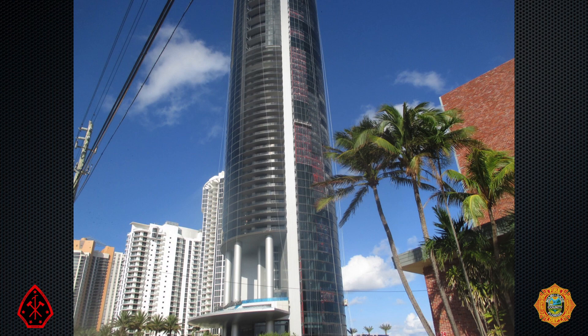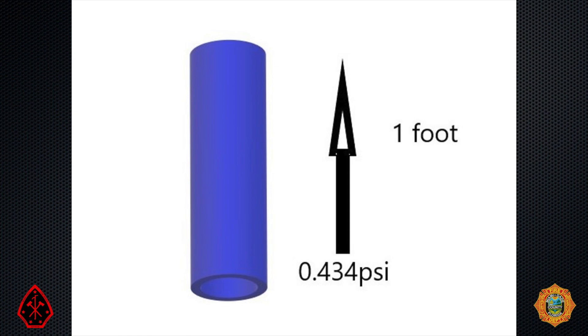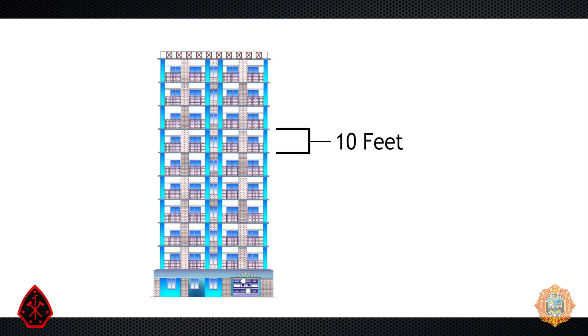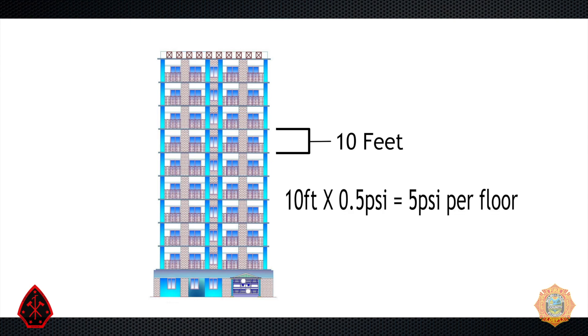and residual pressure with water flowing to a maximum pressure of 175 psi. This becomes problematic in tall buildings because of elevation or head pressure. We learned in basic hydraulics it requires 0.434 psi to lift a column of water one foot. Accordingly, the pressure at the base of a column of water one foot high is 0.434 psi. To simplify hydraulic calculations, we round 0.434 to 0.5 psi.